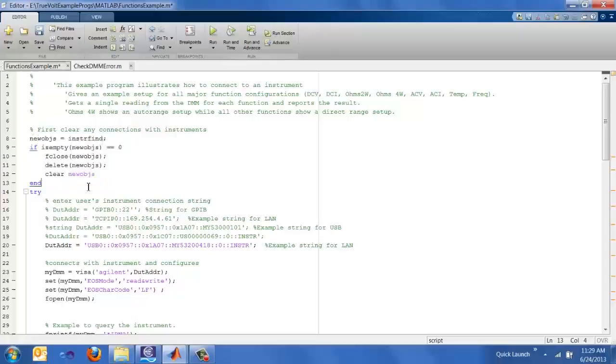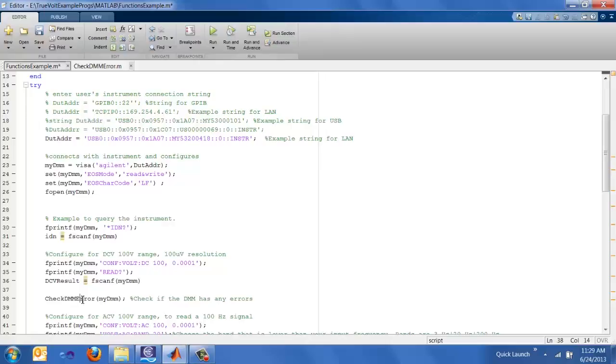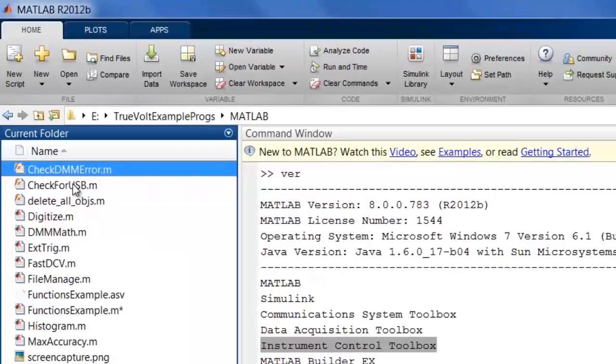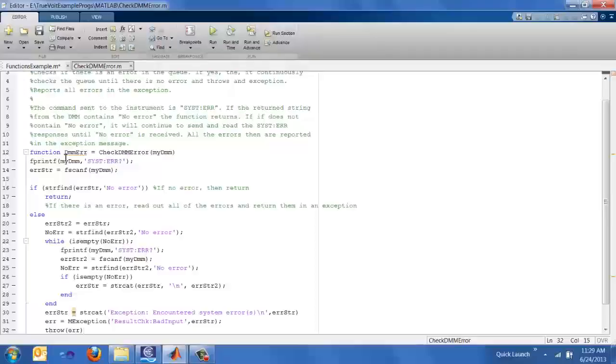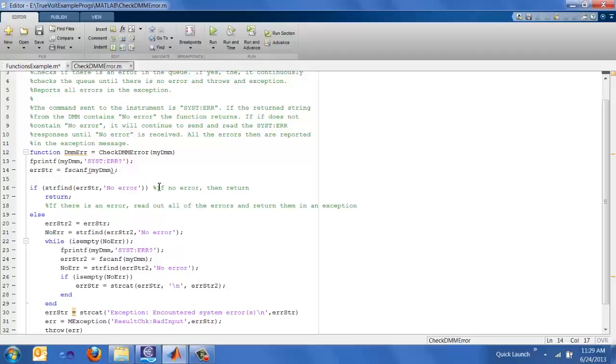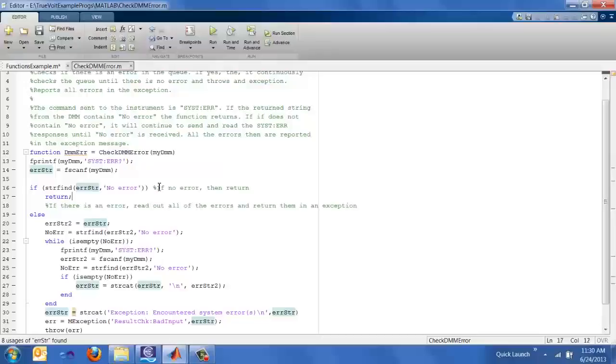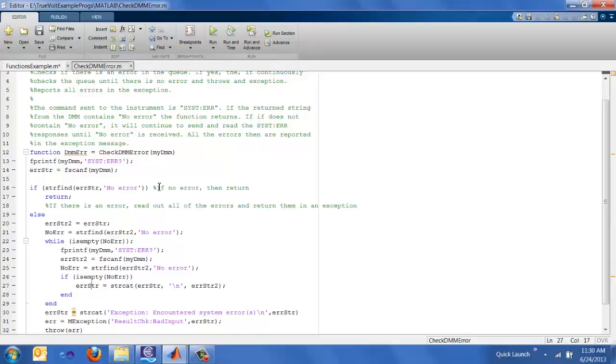Another function that we have is the checkDMM error. If we go back to the MATLAB window, we'll see that we have the delete all objects function here. We also have our checkDMM error, which is another function. Let's go ahead and open that. And we see here that the function basically sends a system error query and then reads that error back from the instrument and says, hey, if there's no error found in that string, go ahead and continue with your program. However, if there is an error, we'll actually continue to send over that system error query and then repeat that until we can find the no error string. Once that's finished, we'll actually throw an exception and report on all those errors as a string.